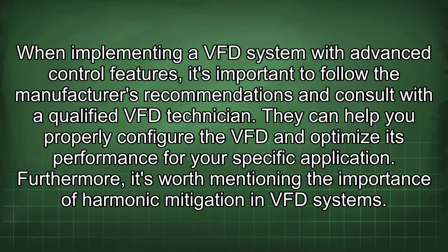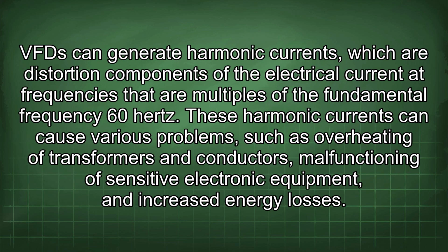Furthermore, it's worth mentioning the importance of harmonic mitigation in VFD systems. VFD can generate harmonic currents, which are distortion components of the electrical current at frequencies that are multiples of the fundamental frequency, 60 Hz. These harmonic currents can cause various problems, such as overheating of transformers and conductors, malfunctioning of sensitive electronic equipment, and increased energy losses.